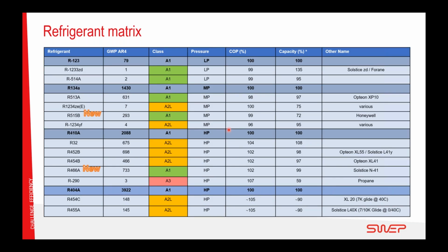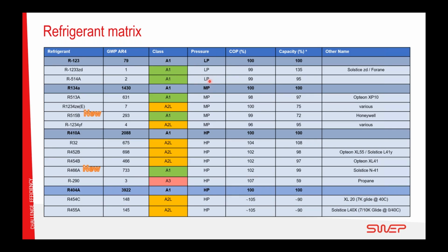In this refrigerant matrix, I've tried to consolidate the different candidates that are available. The dark blue is the reference in every category. So the first part here is low pressure refrigerants. Next is medium pressure, and then we have high pressure in 2 categories. If we start with R134A, we can see that GWP is 1430. It's an A1, so it's non-flammable, medium pressure, 100 in COP in capacity.